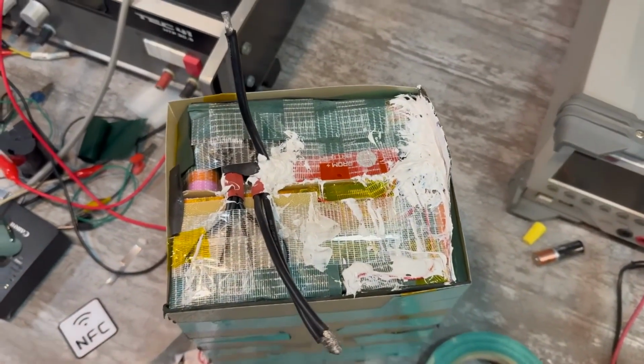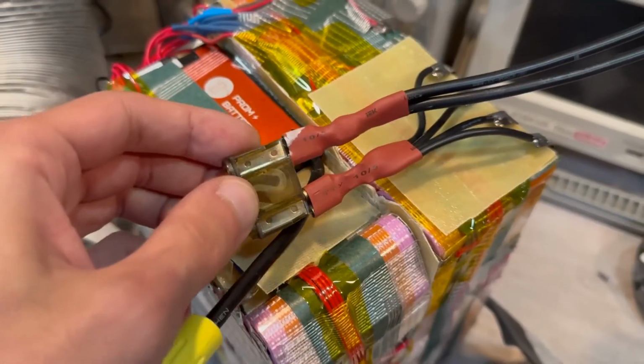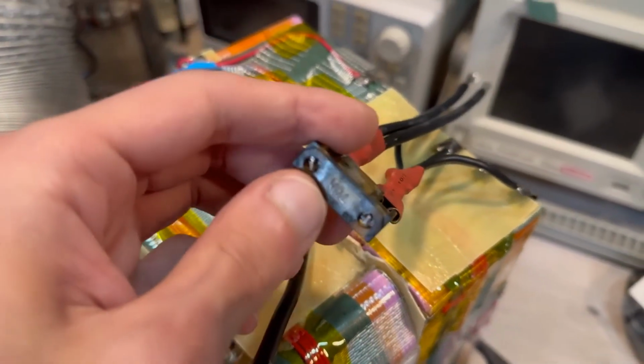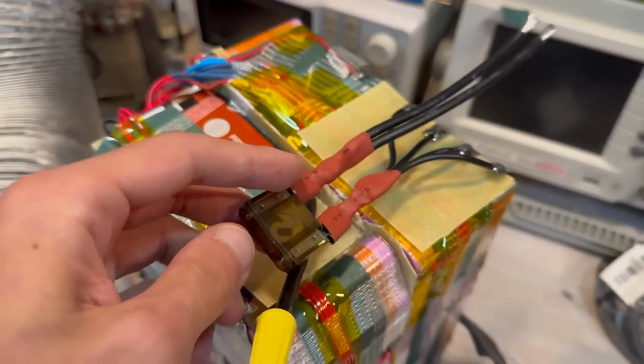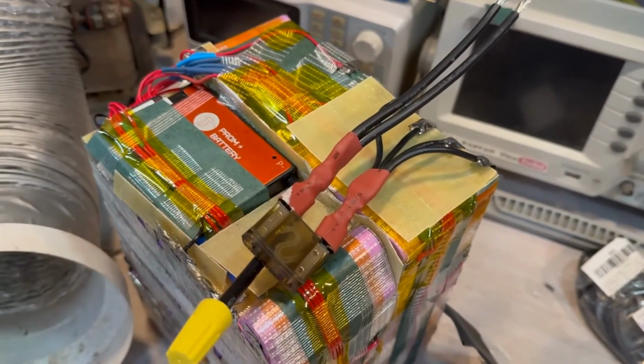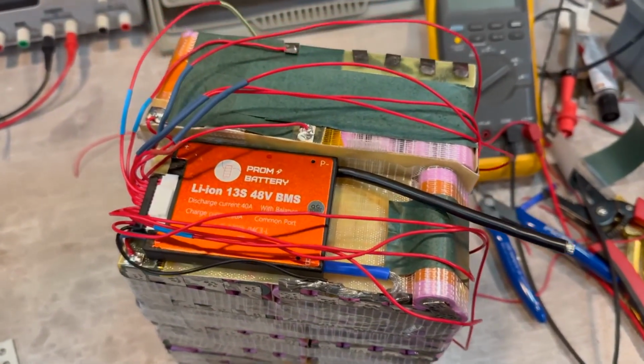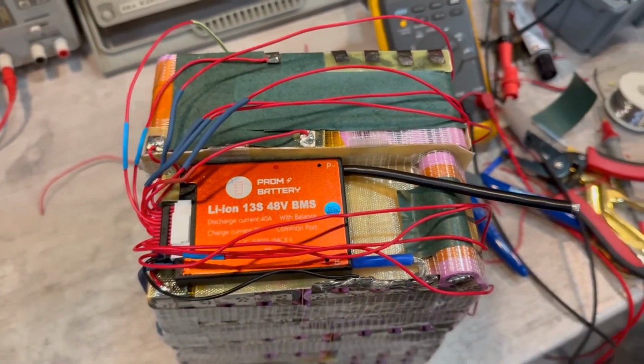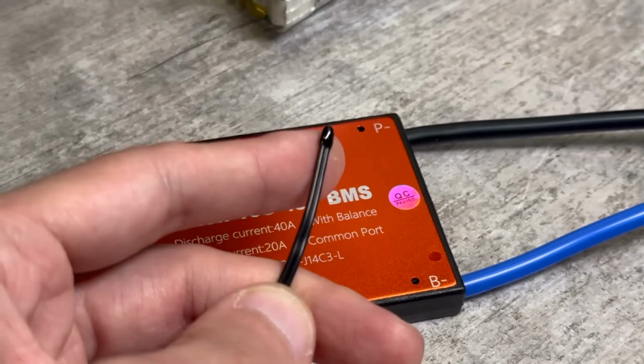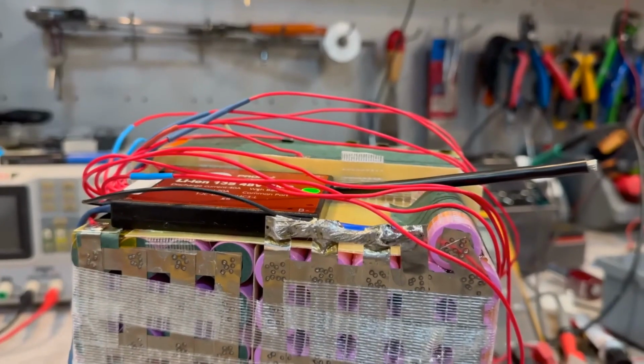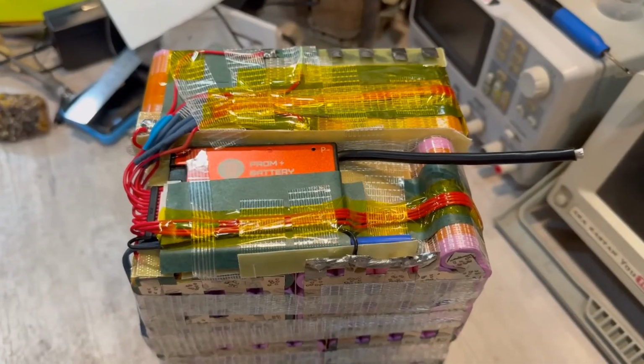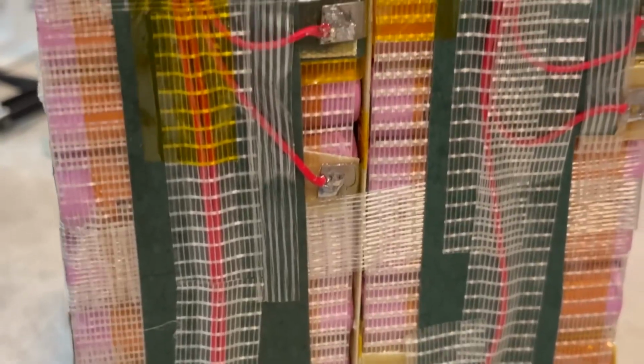There is a large 70-amp fuse on the positive power line. This is additional protection in case of an emergency and the electronic short circuit protection on the BMS board fails. In such cases, the fuse will save the day. The BMS temperature sensor is tucked away deep inside the battery. Before the final assembly, of course, the battery needs to be thoroughly tested.